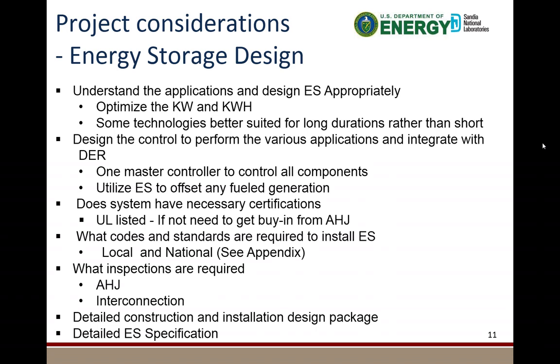That's a problem in some installations. Your authority having jurisdiction may want UL listed. You have to deal with that, and I'll talk a little bit more about that with the project team. And then what codes and standards are required to install the energy storage, what inspections are required for the interconnection for your local inspection. And then in some of these systems that are more detailed, you will need a construction and installation design package. And then this last bullet here is an energy storage specification. We're working on trying to come up with generic specifications that people can utilize to tailor to their needs, but when you go out to buy your energy storage system, you should have a nice detailed specification indicating what it is you want.